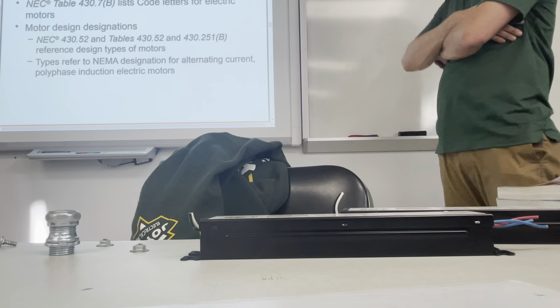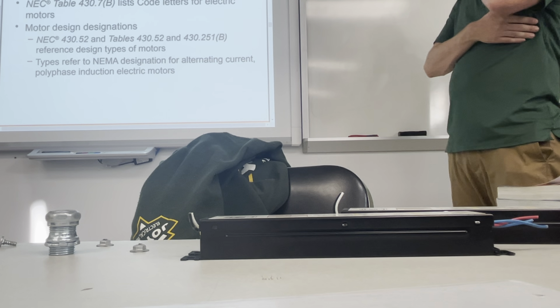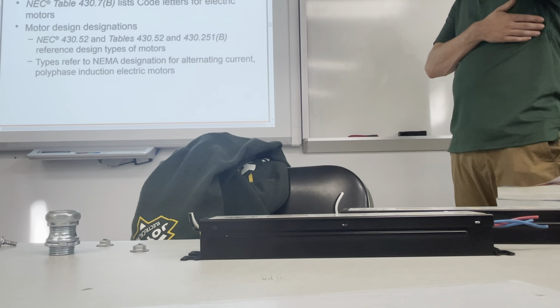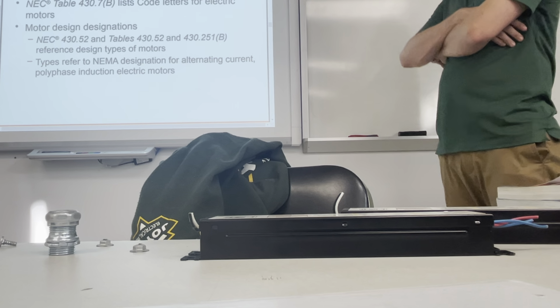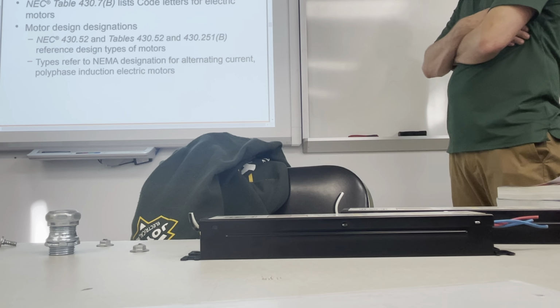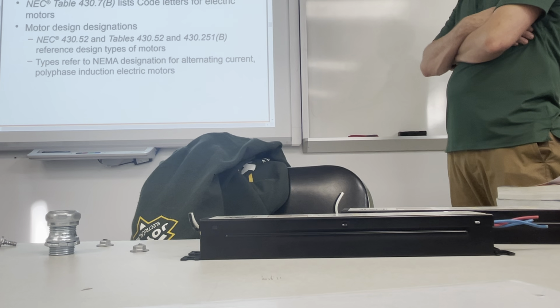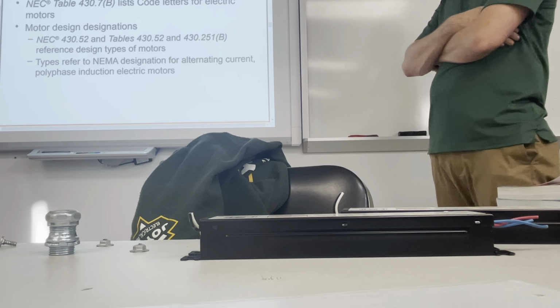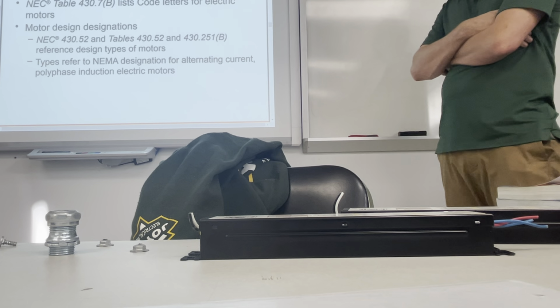NEC Table 430.7(B) lists code letters for electric motors. Motor design designations: NEC 430.52, in Tables 430.52 and 430.251(B), references design types of motors. Types refer to the NEMA designation for alternating current polyphase induction electric motors.